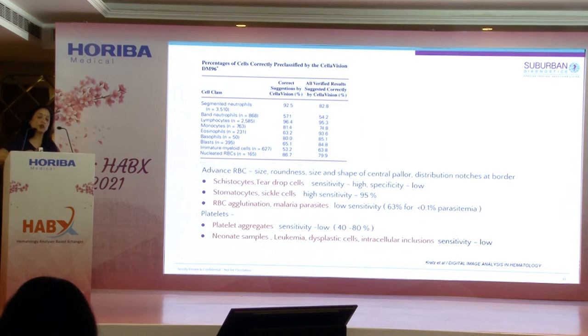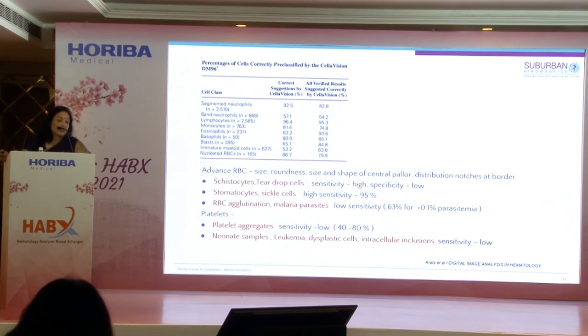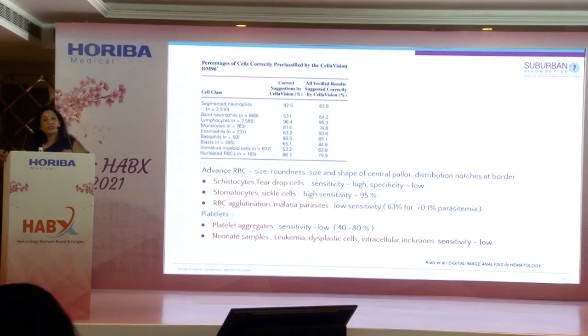Regarding advanced RBC analysis, the system evaluates size, roundness, shape of the central pallor, distribution, and notches at the border to categorize RBCs. We found schistocytes and teardrop cells had very high sensitivity but low specificity. Stomatocytes and sickle cells had very high sensitivity — even new pathologists who might miss a sickle cell would not miss it here. For RBC agglutination and malaria parasites, detection is more challenging at very low parasitemia (less than 0.1%), but on thick smears we were able to pick up malaria successfully.